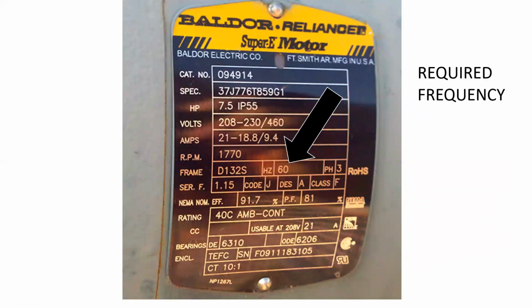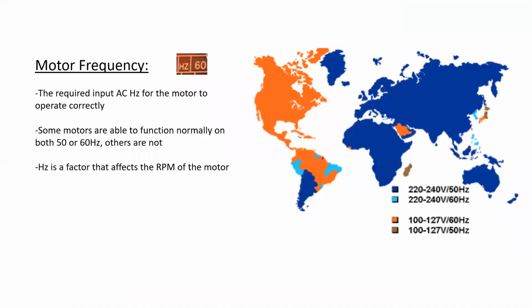Required frequency. This motor has a 60 hertz system requirement. The motor frequency is the required input AC hertz for the motor to operate correctly. Some motors are able to function normally on both 50 or 60, others are not. And depending on where in the world the motor is coming from, it may have different ratings. And if they make a motor that is going to operate for both 50 and 60 hertz, it means that it can be sold to more individuals. Hertz is a factor that affects the RPM of the motor.